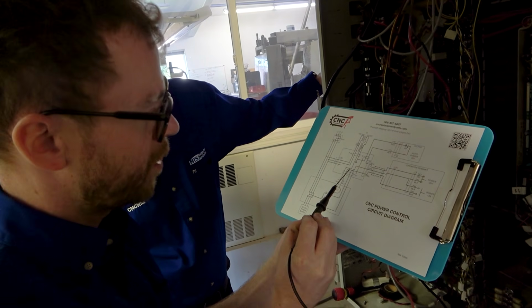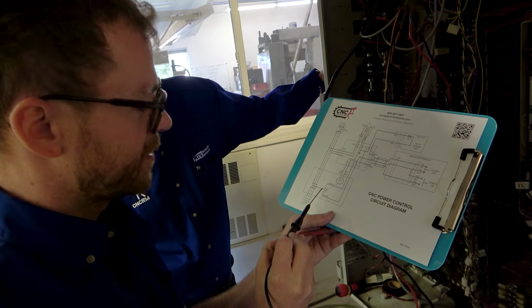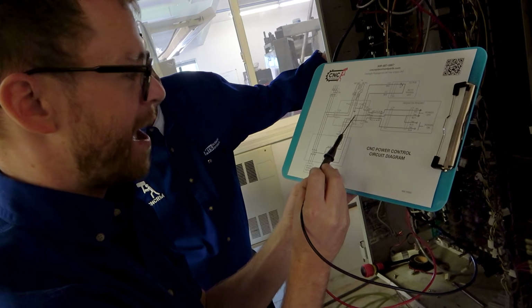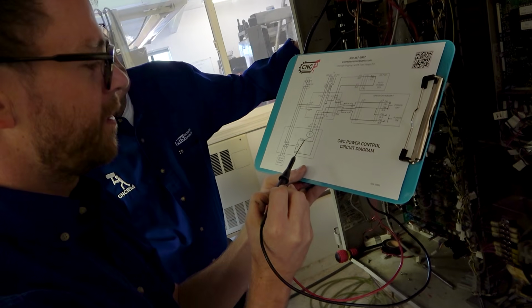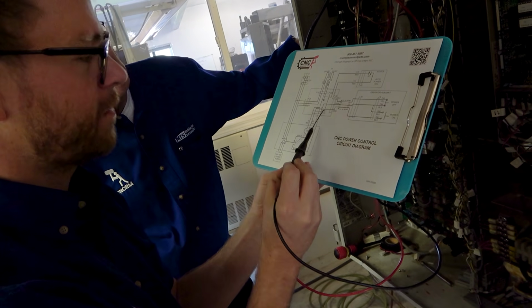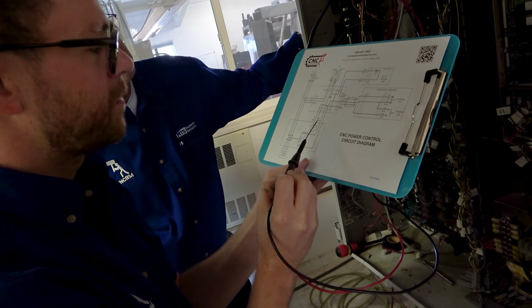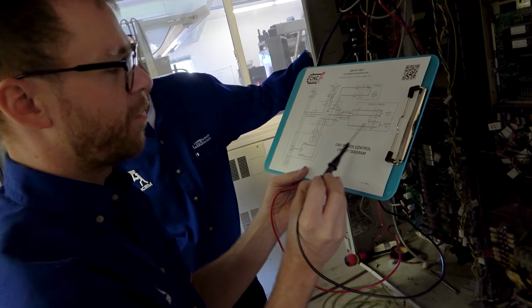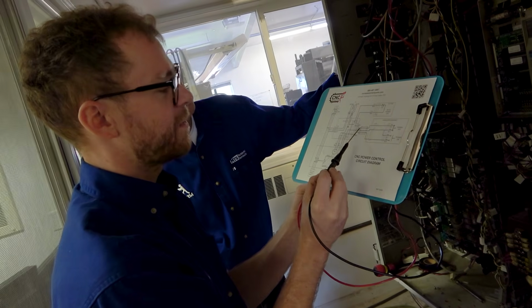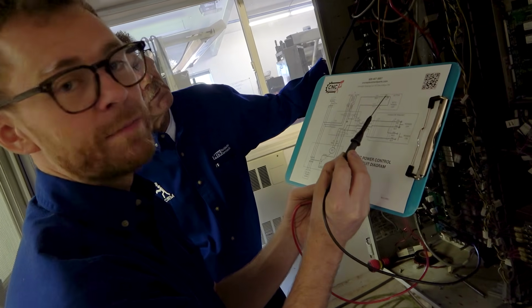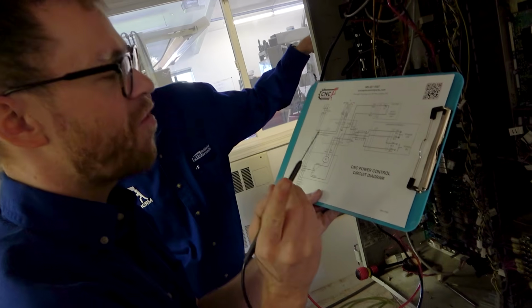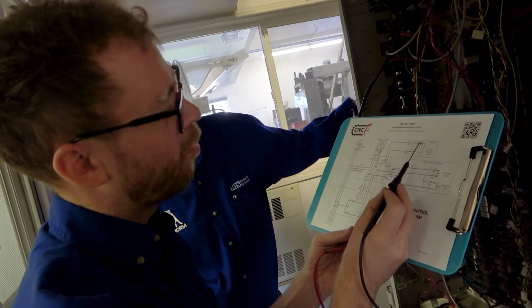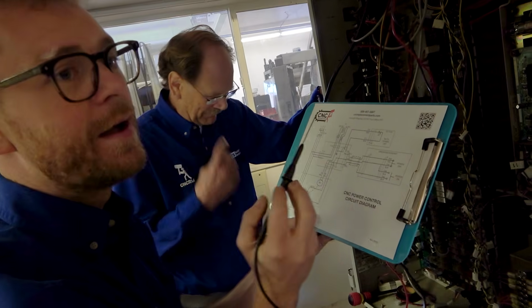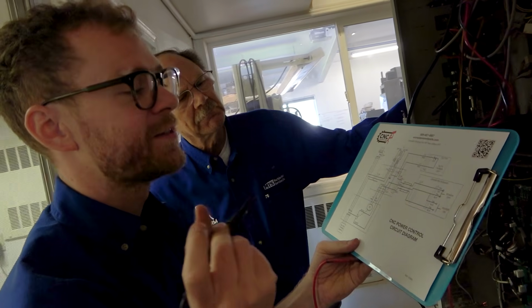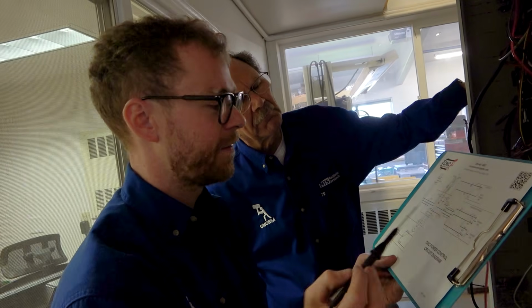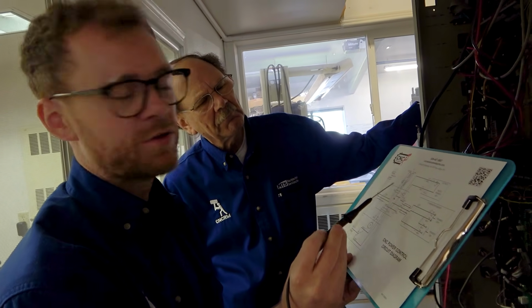So carrying on with our circuit, we know the power came down, it's split. It's not energized because it's drawn that way. It then comes back and it also goes up front to the off button. The other side of the coil, which is the other side of the contact, goes to the on button. So we've got these two voltages, which come from the transformer, going up to the front. Then it leaves the front and comes back and goes to a plug on the I/O board. Remember, everything is drawn in the non-energized state. So a normally closed contact, K7, means that when it's energized, it's open. But when it's not energized, it's closed. It's a normally closed contact. It then leaves and goes back to the ground.